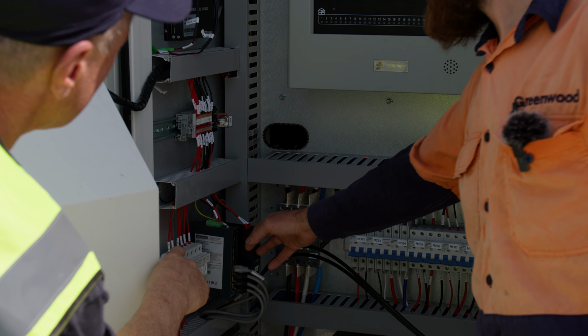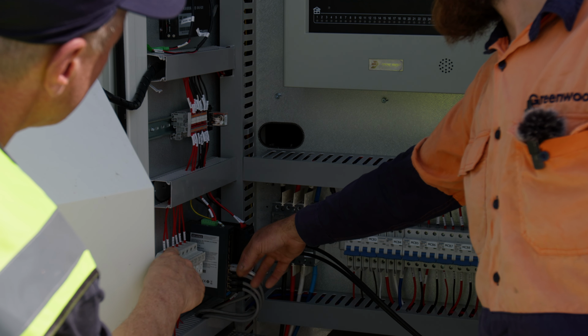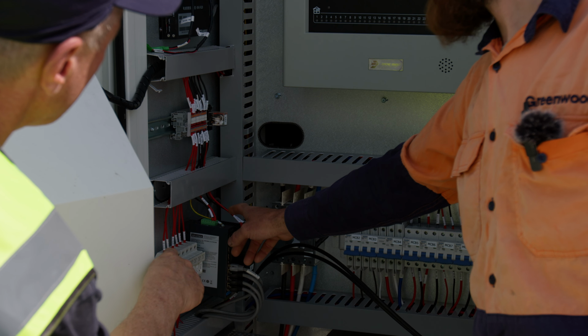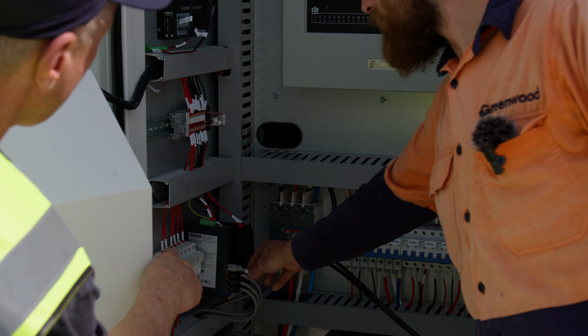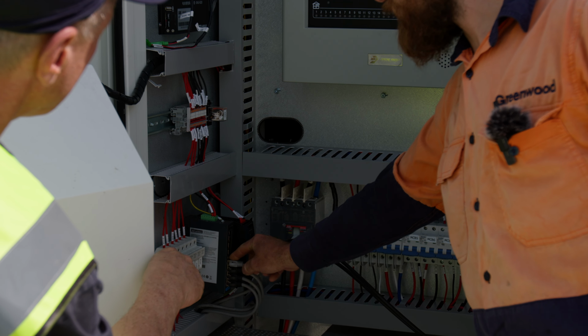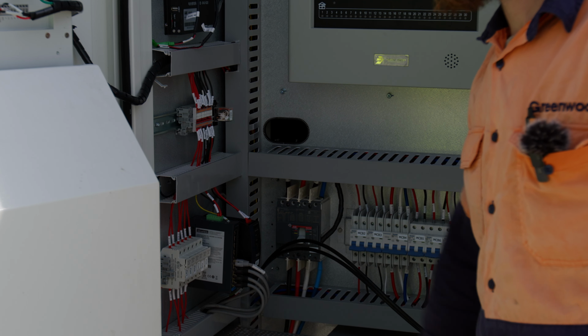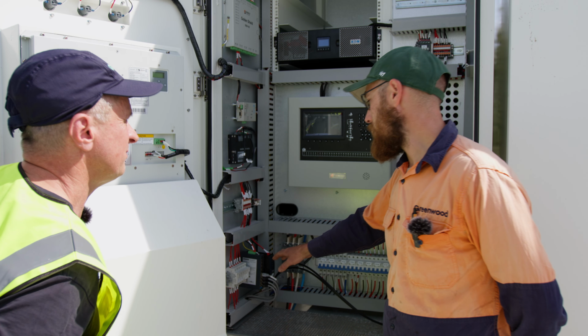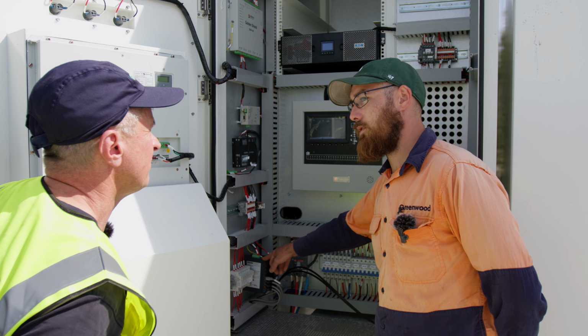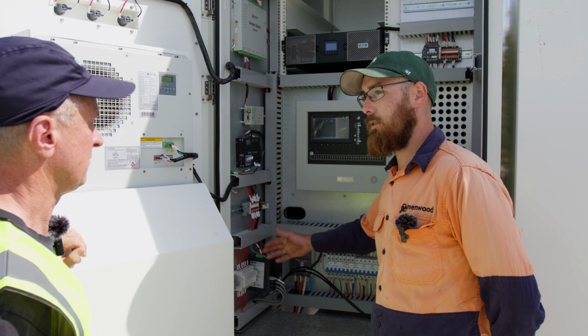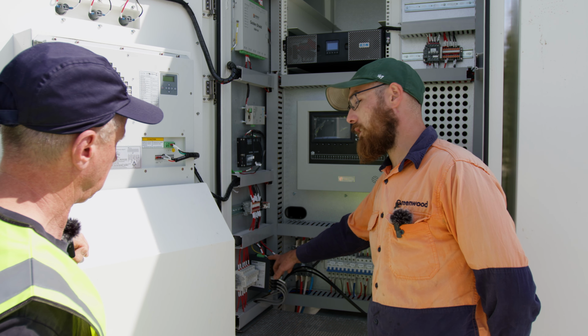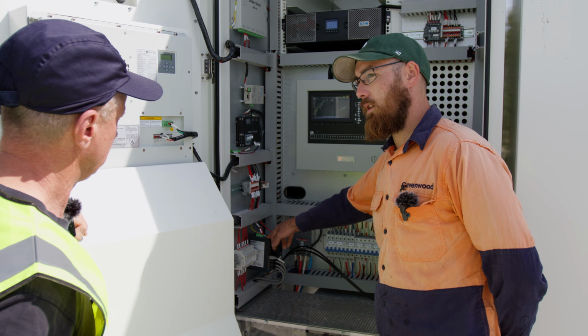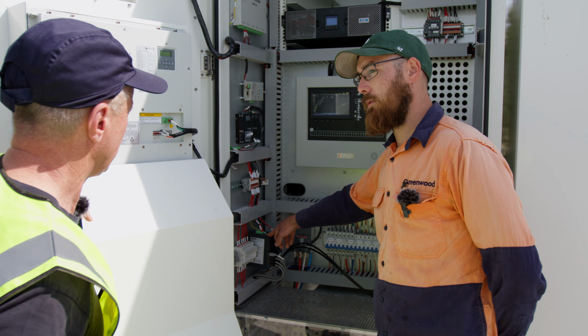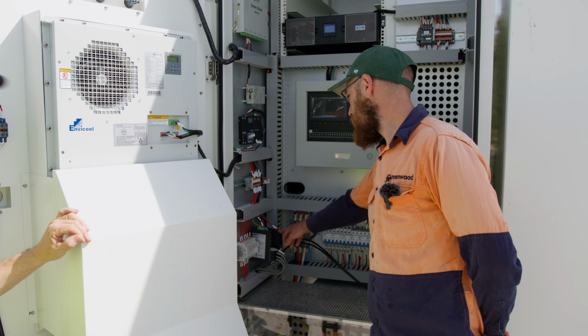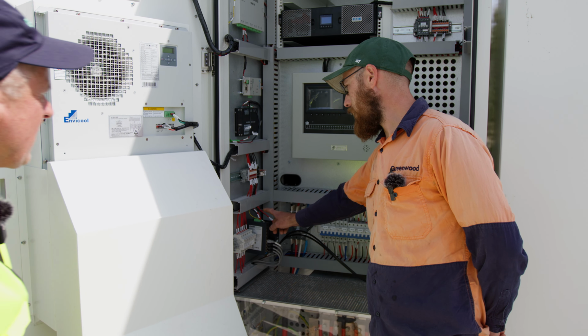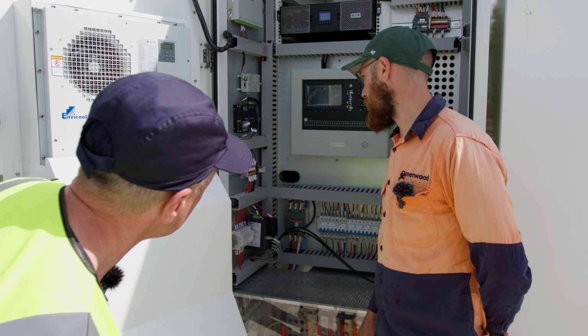The 24 volt power supply is just to power the router here. This is an unmanaged switch. This is where everything plugs in, so we've got the inverters daisy chained out of here. Sorry, what do you mean by an unmanaged switch? This unmanaged switch doesn't assign IP addresses itself. It needs to have another modem that takes precedence over it. So this will be connected back to our main control gear, which will direct the whole system as to what to do. This one here is just a 24 volt power supply, which will power the unmanaged switch. Gotcha. That's all it needs to do.